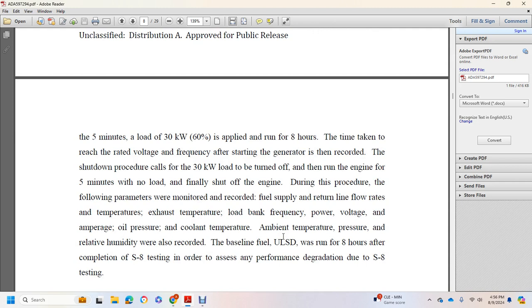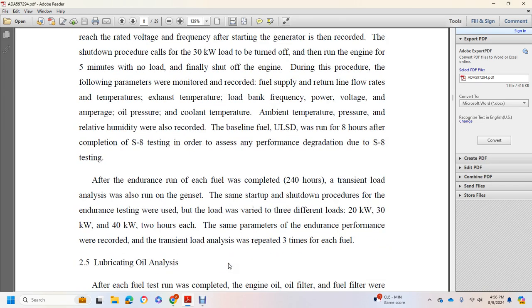The following parameters are monitored: fuel supply and return line flow rates and temperatures, exhaust temperature, load bank frequency, power, voltage, and amperage. Oil pressure, coolant temperature, ambient temperature and pressure, and relative humidity were also recorded. The baseline ultra-low sulfur diesel was run 8 hours after completion of the S8 testing in order to assess any performance degradation due to the S8 testing. After the endurance run, each fuel having completed 240 hours, transient load analysis was also run with the generator.